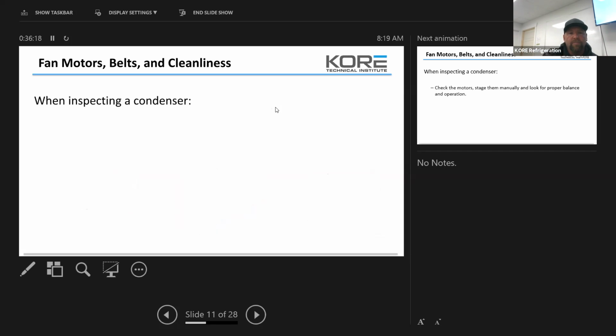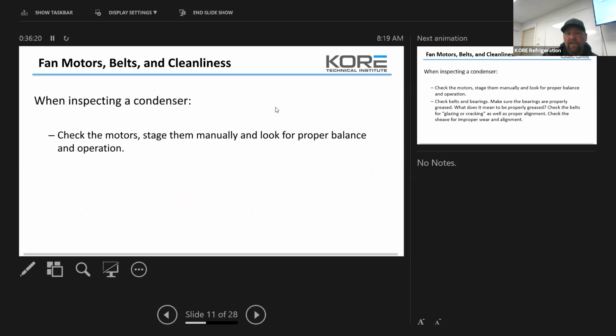Fan motors, belts, and cleanliness. When inspecting a condenser, check the motors. When you guys are doing your PM work, you should be checking the motors, right? You should be bumping the contactors and staging them. So what are you checking for when you stage your motors? Temperature. You want them to crank on, right? Yeah. Are you guys looking at the balance in the motor? You want to make sure your blades are balanced, because if the blade is out of balance, you're going to take the bearings out in the motor. So you want to stage that and check that.